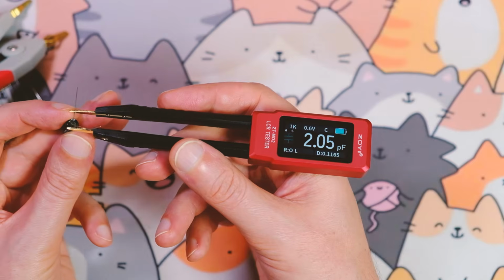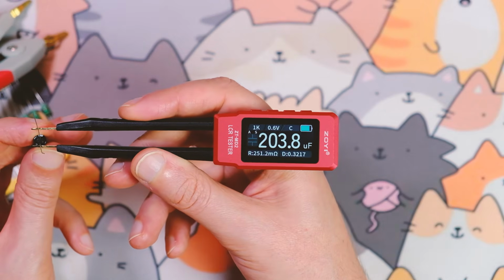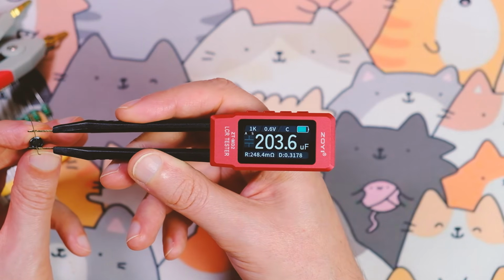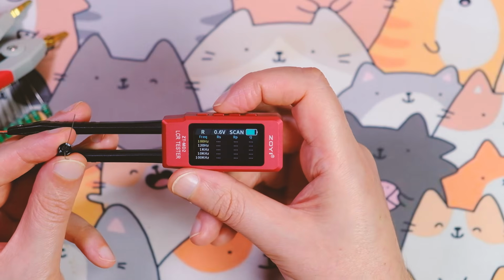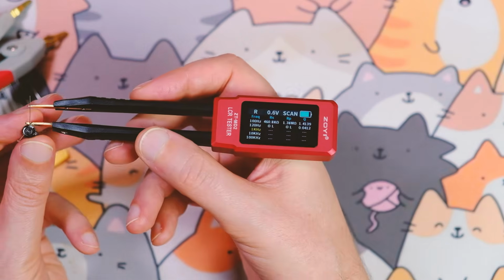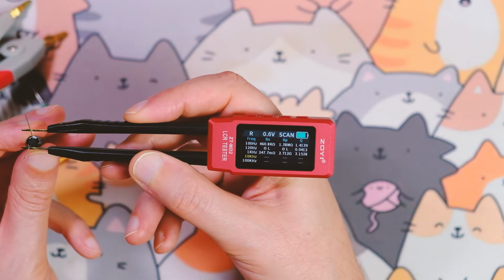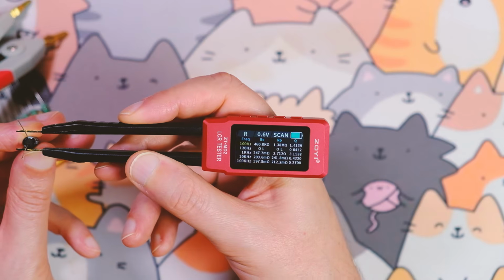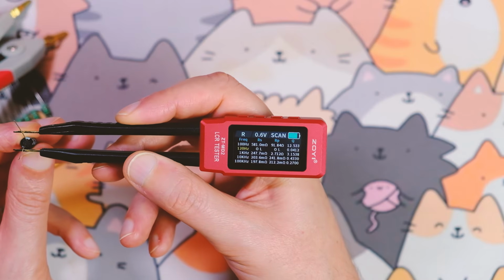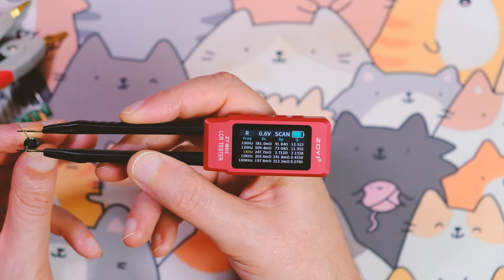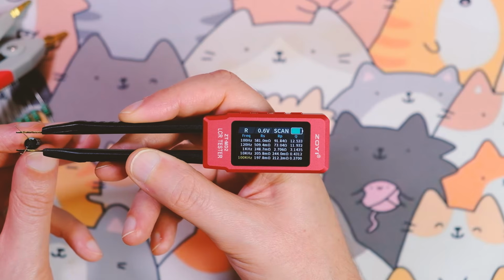At a 1 kHz frequency, the ESR is 250 milliohms, but it's better to measure this in scanning mode. Only in scanning mode, we select resistance as the primary parameter. And here will be RS series resistance, RP parallel resistance. And, as you can see, the ESR differs at different frequencies.